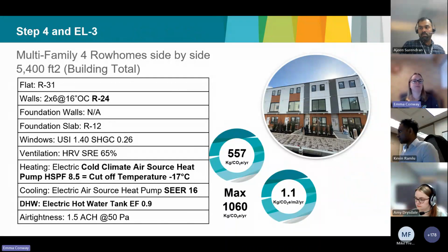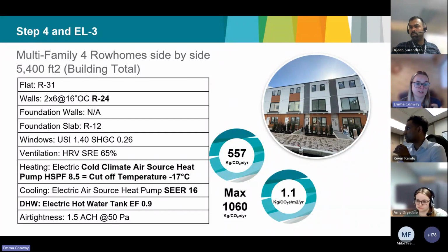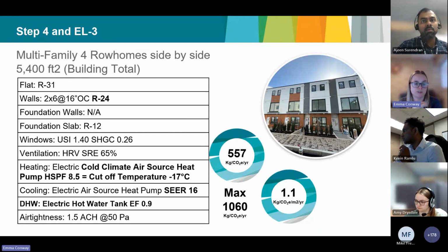What about emission level 3 for the same building? I went back to my first iteration with the full heat pump, and played around with it a bit, bringing in an example with a cold climate air source heat pump, meaning there was no supplementary heating system needed. That cold climate air source heat pump, with super high efficiency, operates at about 90% down to -17 degrees Celsius, which is fine for this climate zone.